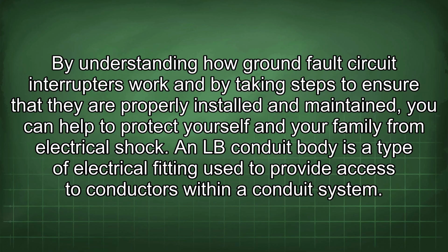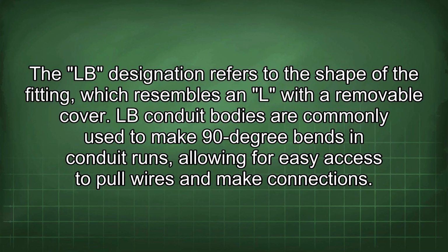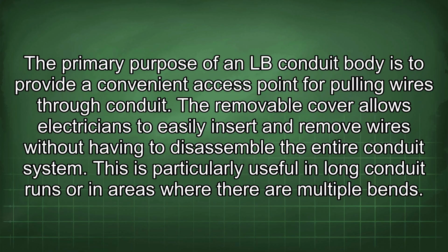An LB conduit body is a type of electrical fitting used to provide access to conductors within a conduit system. The LB designation refers to the shape of the fitting, which resembles an L with a removable cover. LB conduit bodies are commonly used to make 90-degree bends in conduit runs, allowing for easy access to pull wires and make connections. The primary purpose of an LB conduit body is to provide a convenient access point for pulling wires through conduit.